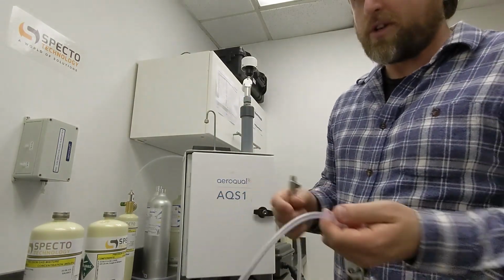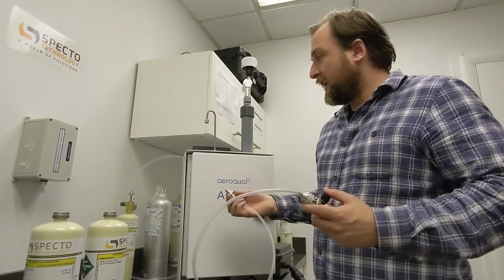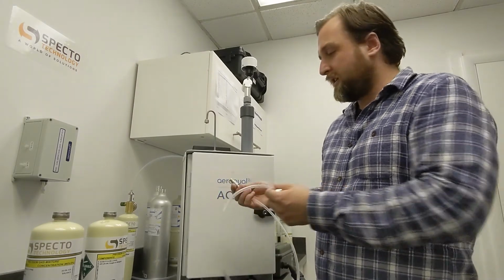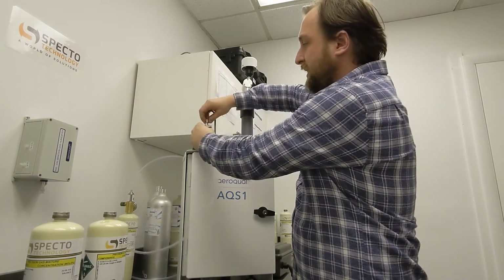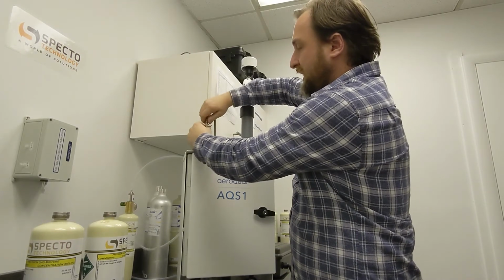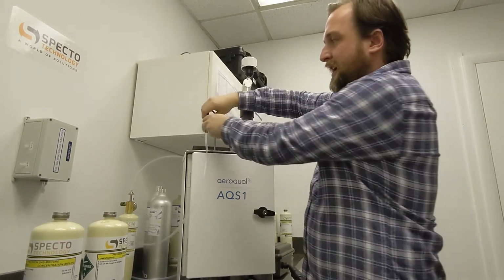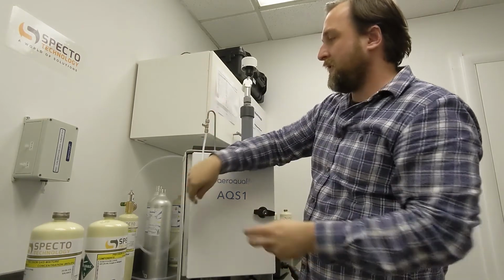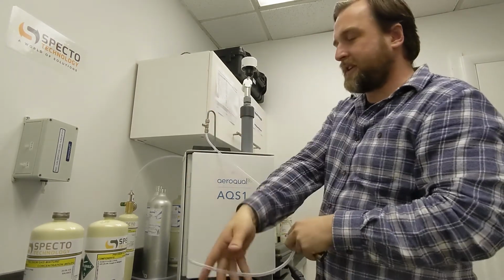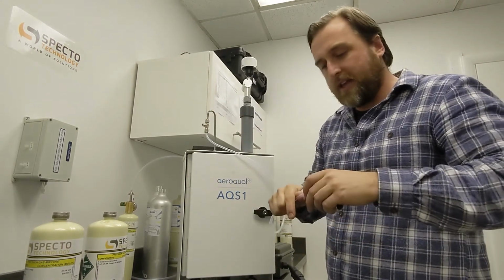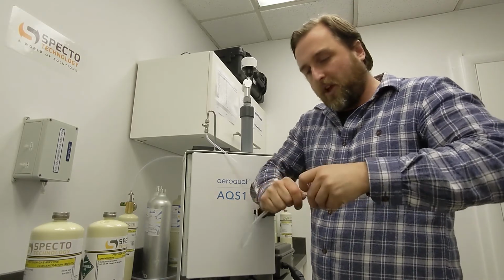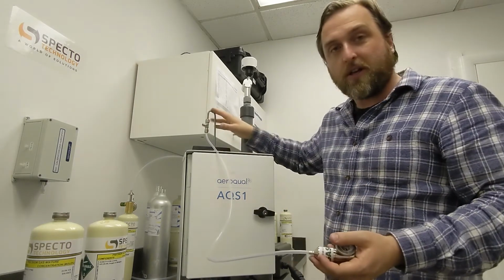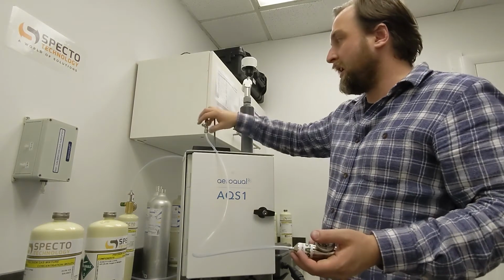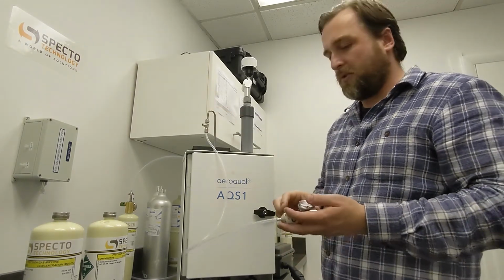Really all we're doing from the physical side of this calibration is connecting the T-piece up to the gas sample train. You just do that finger tight. The T-piece has an opening, so that there's excess gas flowing into the monitor. We don't want to pressurize the gas module, so we have excess gas flow for the module.